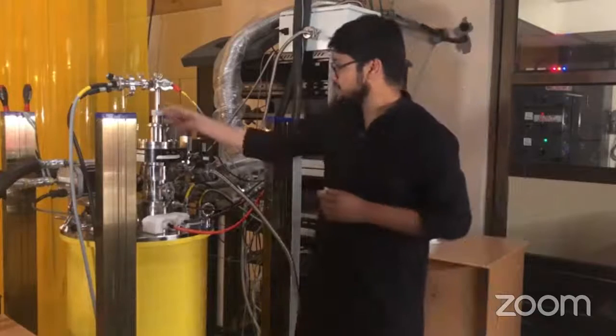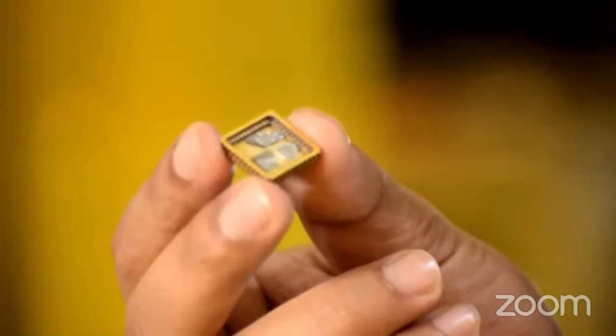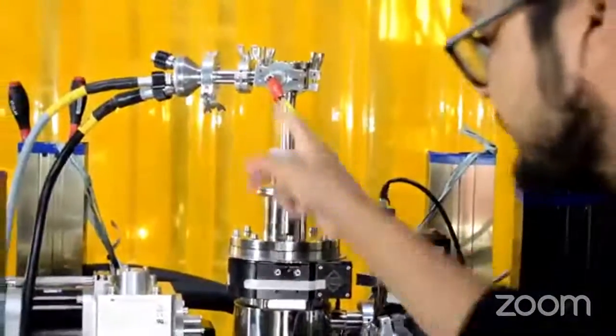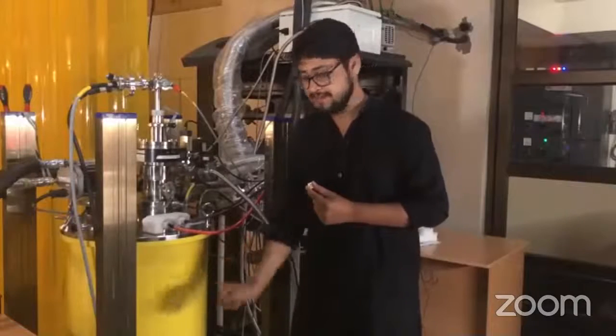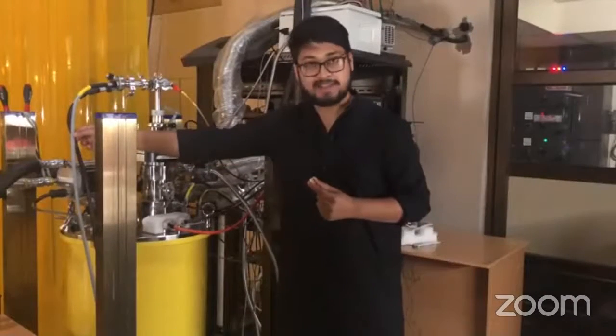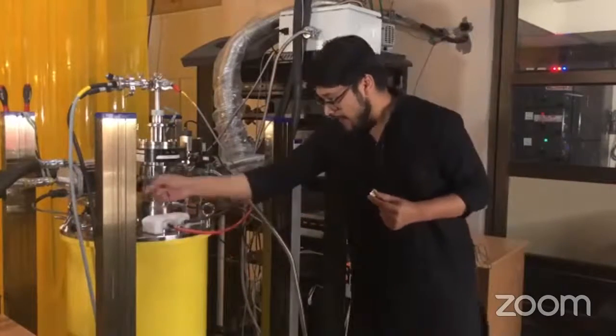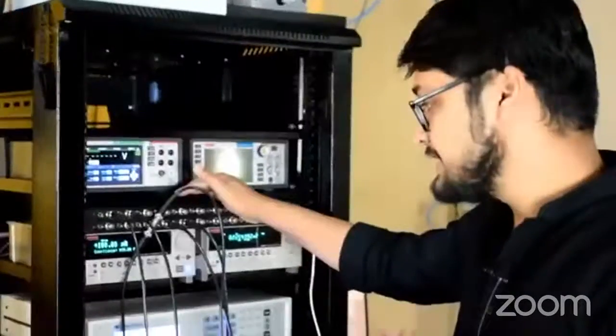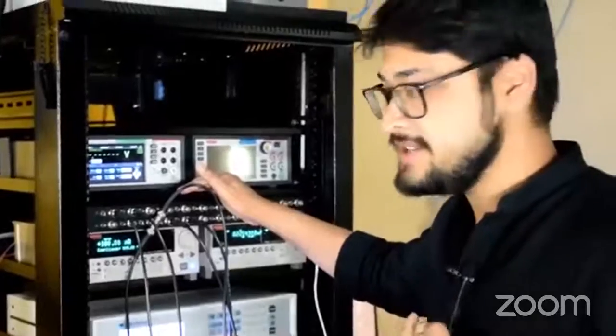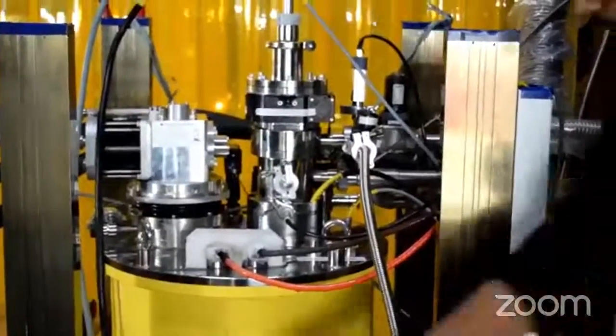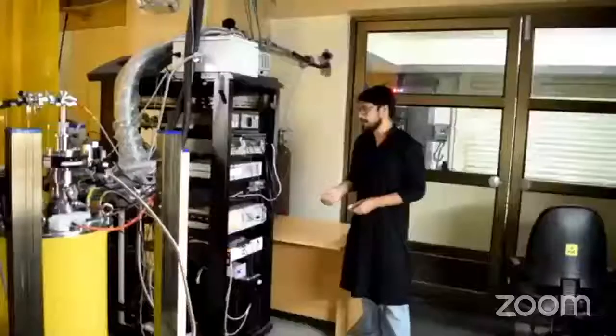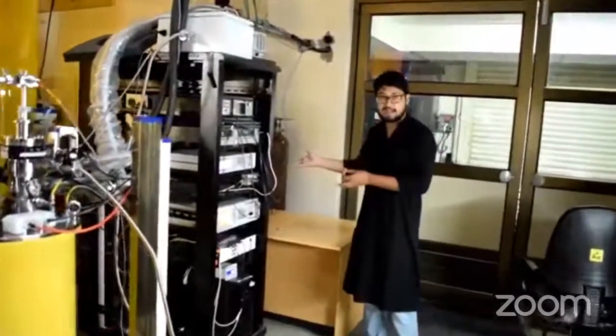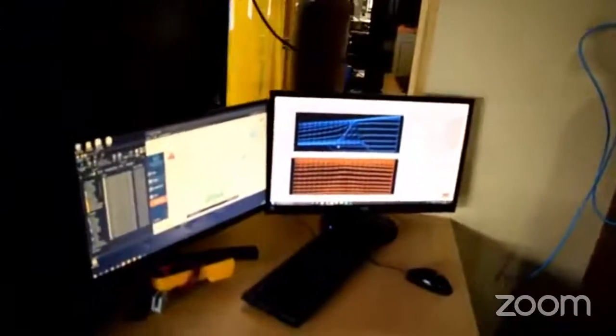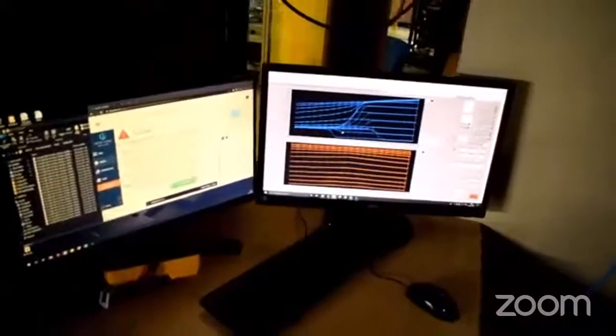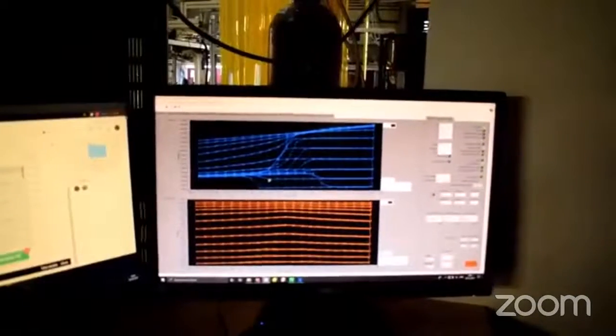So if you see this stick, this is our sample, and we put this sample at the end of this stick, and this stick goes all the way to the bottom of this cylinder. Okay, and if you see these cables, these cables are connected to the sample and to the controllers here. So these controllers basically measure temperature, current, and voltages. We also measure these electronic properties of our samples at different magnetic fields. So we have a big magnet inside this chamber. These controllers are connected to a computer here, and all of our experiments are automated. You can see these data plots. These are basically a measurement that is going on right now.